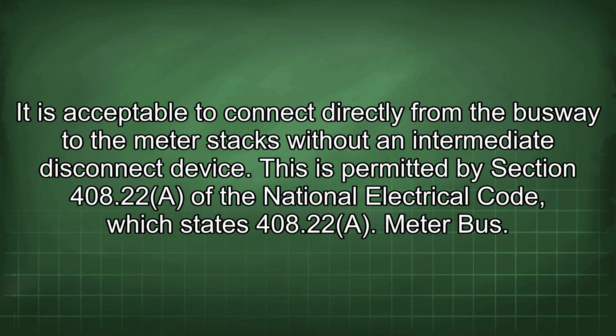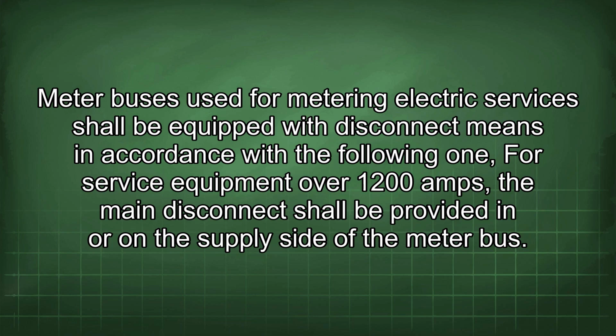This is permitted by Section 408.22 of the National Electrical Code, which states 408.22(A) Meter bus. Meter bus used for metering electric services shall be equipped with disconnect means in accordance with the following. 1.